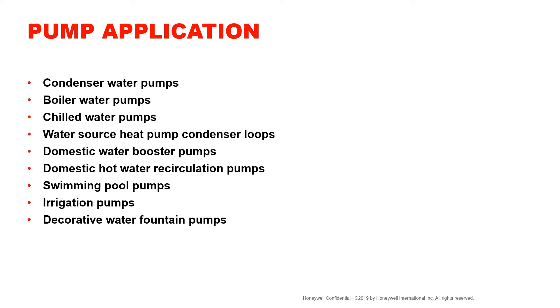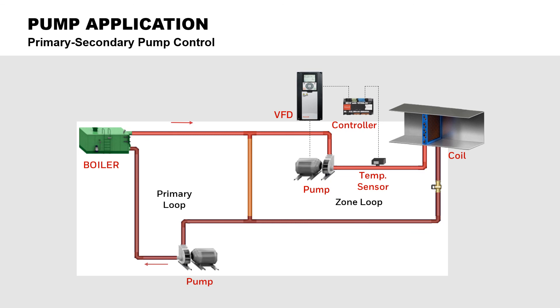These are all the pump applications where VFDs are commonly used to save energy. VFDs are used in many applications; I'll go through the most common pump applications that use VFDs. The most common pumping system is the primary-secondary pumping system. Here is one for hot water. The primary loop continually circulates hot water from the supply to the return of the boiler. The pump in the secondary loop will speed up or slow down depending on the temperature of the water in that loop.